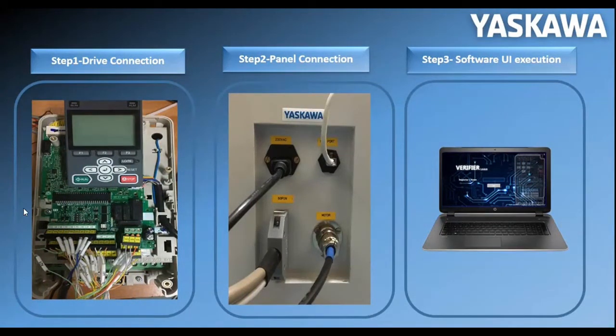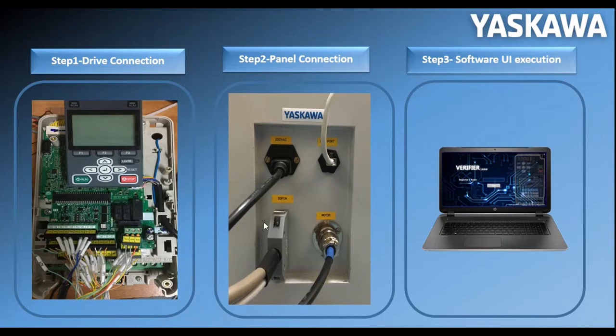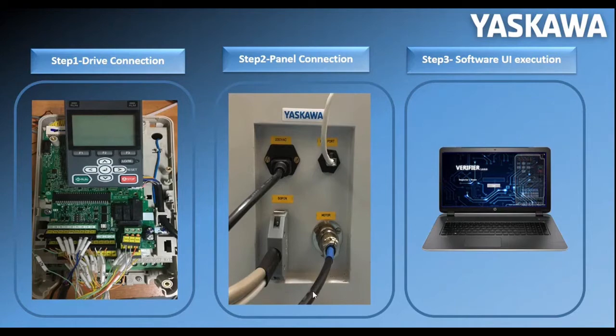This slide shows the connection. We have the 230-volt supply connection for the panel, a communication port for the supply, and the 50-pin connector which connects to the VFDs. There is a strip which we can insert into the control card and it will be ready — no need to connect individual cables to the control cards. This cable is for the motor connections to the VFDs.